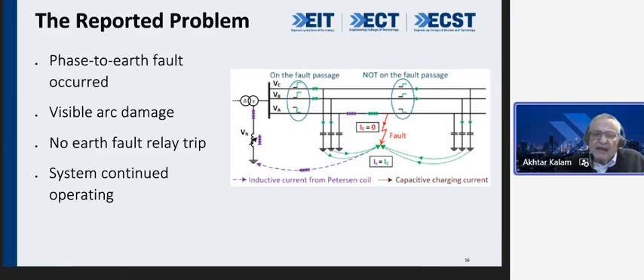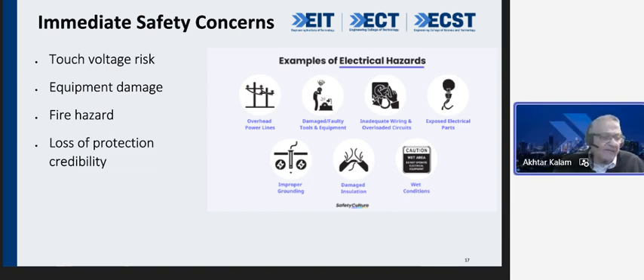So, what I would do, and look at it carefully, putting on my hat as Lieutenant Columbo, I would first think of safety. I want to be safe. I do all the hazard assessments that I have to. I do the touch voltage risk. I look at equipment damage. I look at whether there's any fire coming from there. I look at protection credibility. My friend, this is not a technical curiosity. This is a serious safety issue, a very serious one.